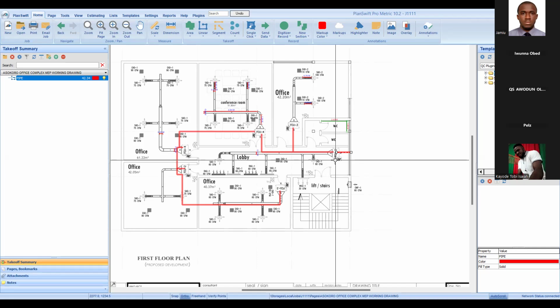Now what other accessories are you using? Let's not forget your cable too, we also have a sleeve. I won't calculate it as a sleeve here because we already have a 75 mm sleeve in this case, with our condensate pipe, our refrigerant pipe, and our electrical cable all passing through it. So I won't calculate for any sleeve here.